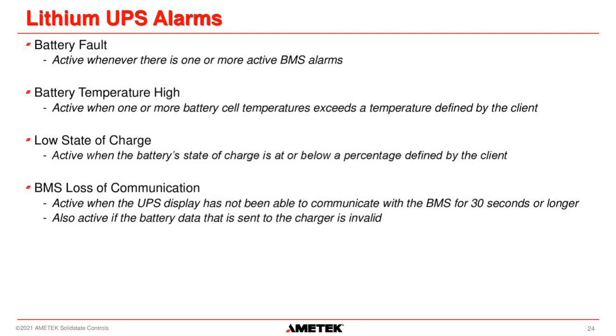We have an alarm for battery temperature high. This will activate if any battery cell temperature exceeds a temperature defined by the client, and this temperature can be adjusted via the UPS HMI screen or the SCI Link application. We have a low state of charge alarm. This will activate when the state of charge of the battery goes below a certain threshold set by the client. Depending on how it's configured, it should activate before the low DC disconnect of the UPS activates. So it's like a first level warning.